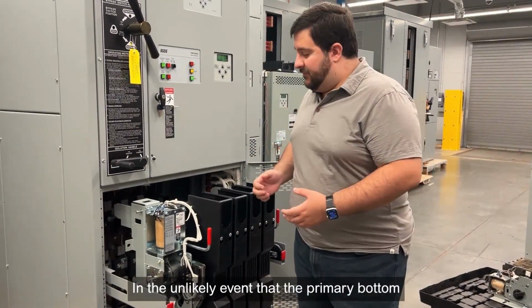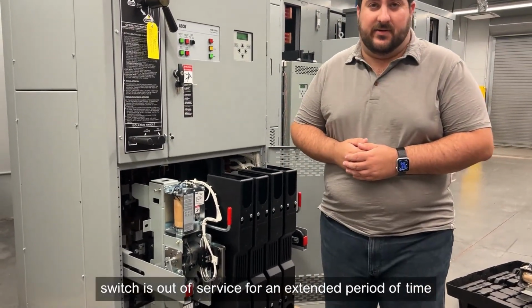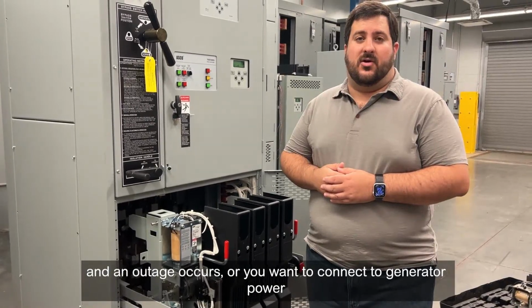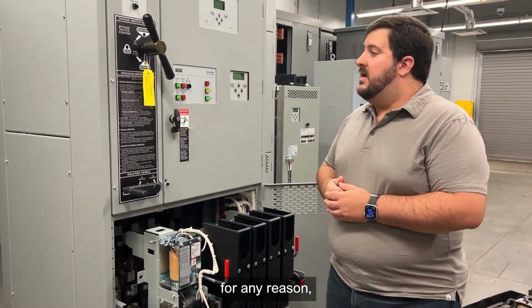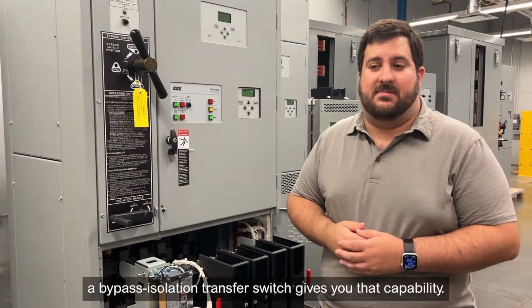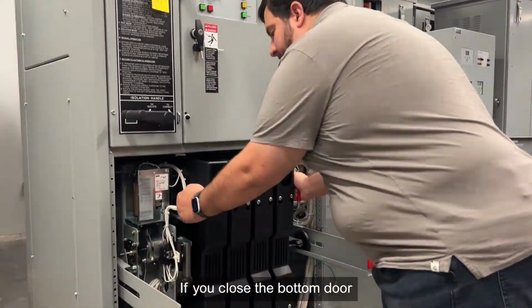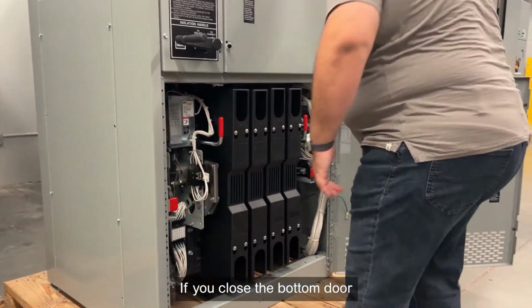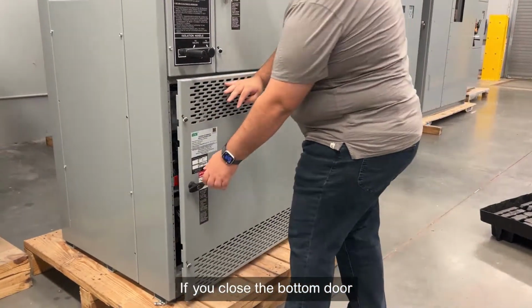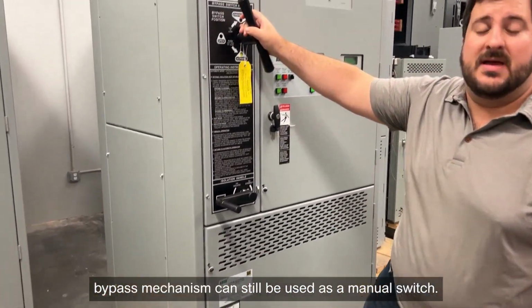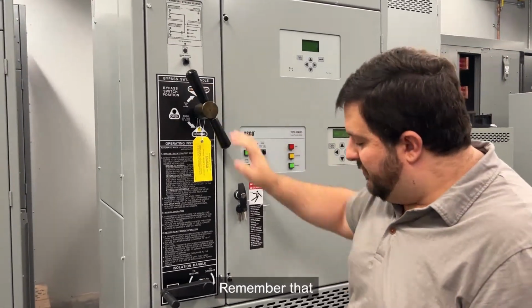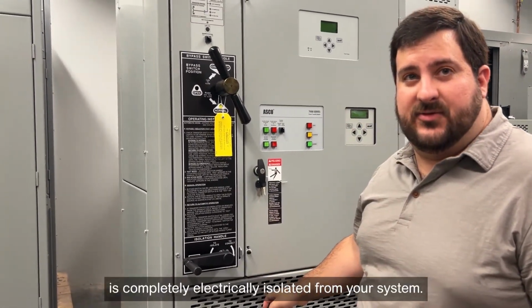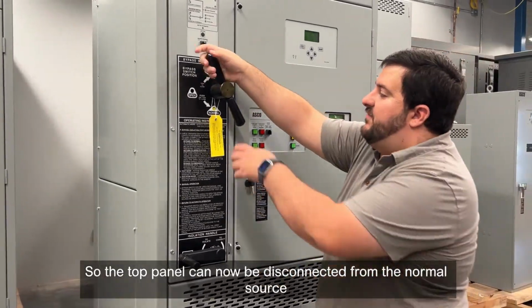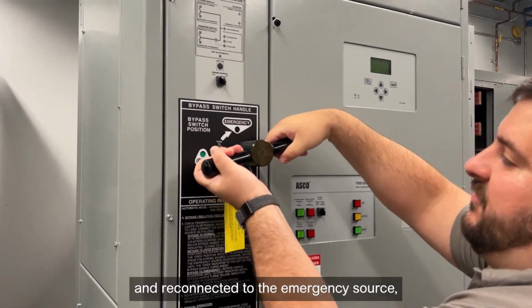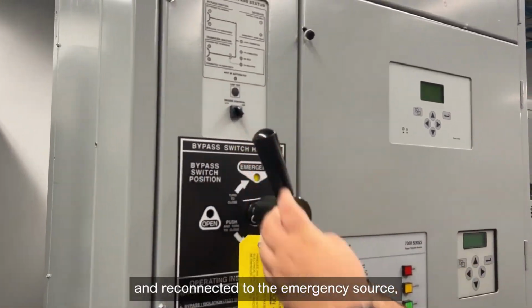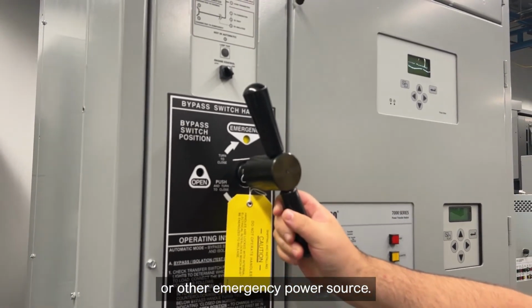In the unlikely event that the primary bottom switch is out of service for an extended period of time, and an outage occurs or you want to connect to generator power for any reason, a bypass isolation transfer switch gives you that capability. If you close the bottom door, the top bypass mechanism can still be used as a manual switch. Remember that the bottom switch is completely electrically isolated from your system. So the top panel can now be disconnected from the normal source and reconnected to the emergency source, allowing you to connect to a generator or other emergency power source.